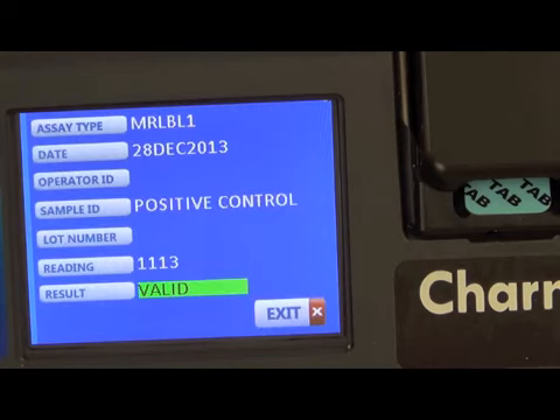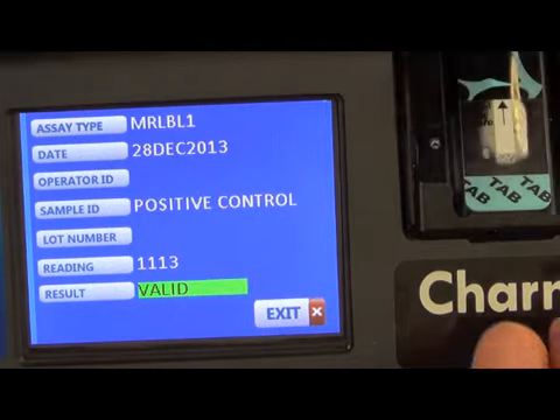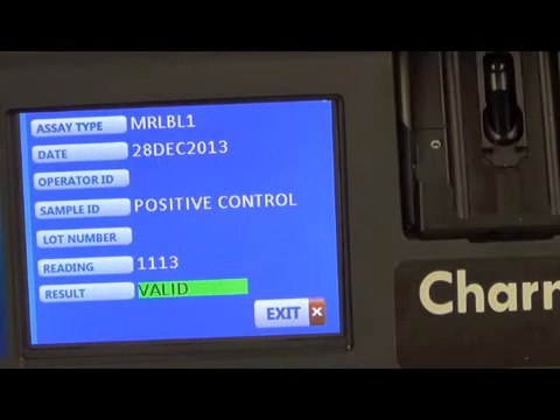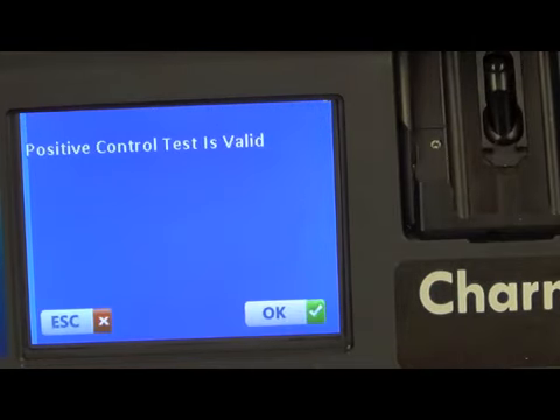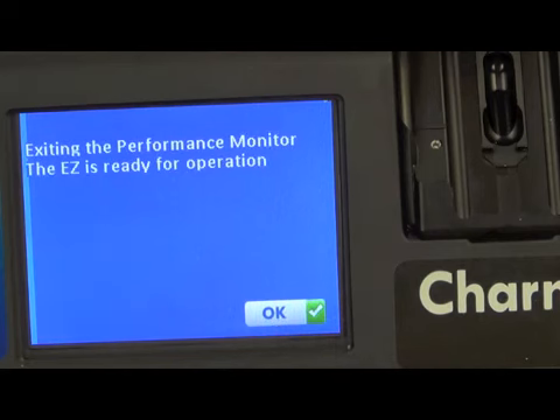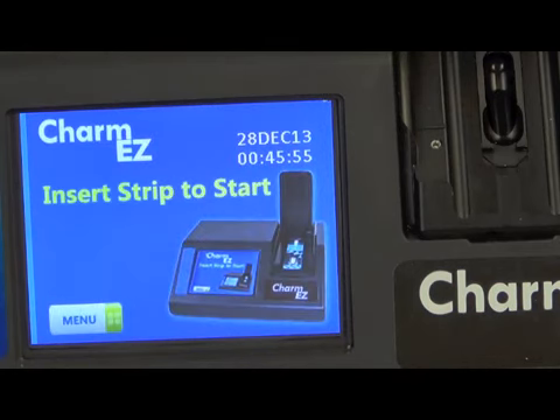Once complete, you will get a positive interpretation, and if the control is valid, meaning a positive result more positive than +400, you will get a positive valid reading. Here we have a reading of 1113, so it's a valid positive control. At this point, remove the strip. You can press escape, exit, and your positive control is valid, and that concludes the performance monitoring operation of the reader. Hitting OK defaults you back to your main screen where you can begin testing for the day.